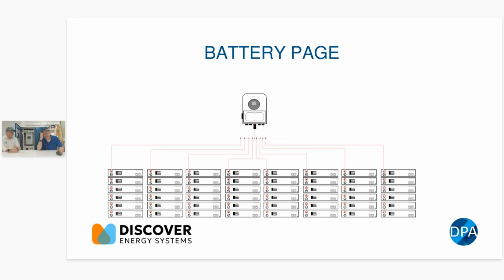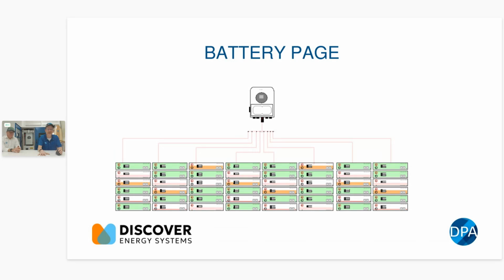The example I often give is imagine you've got a big system in the middle of nowhere. When you put the bank in, you don't really know the state of charge of each individual battery - they tend to be all over the place. After a couple of cycles, they're all going to get to the same point. But normally when you install a bunch of batteries, you can't see any of this, it's just a guess as to what state of charge they're all at, apart from maybe some LEDs on the front. You don't know how quickly they're going to synchronize with each other.